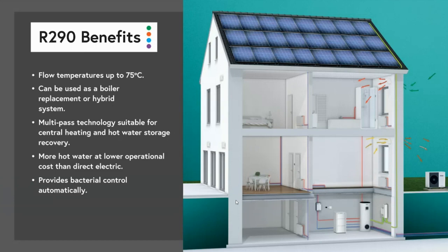So what else does R290 bring us? Well, the biggest advantage from our point of view as a supplier of heat pumps into the heating and hot water industry is flow temperature. R290 can produce flow temperatures up to 75 degrees. So what that means is that it's really a viable alternative or replacement for a boiler system. So a boiler can be removed, and it doesn't matter what type of boiler it is. It could be gas, it could be diesel, it could be wood, it could be pellet, doesn't matter.